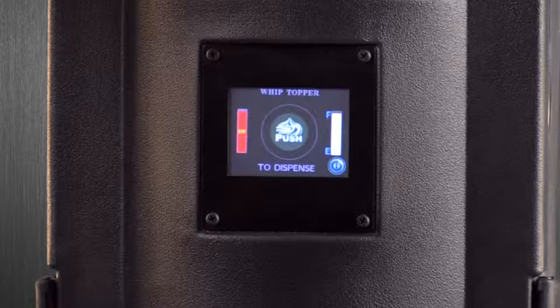Make sure the unit's door sill is properly secured to the door housing as a primary verification. Also, if the unit is showing an excessive temperature reading on the door, for example, plus or minus 200 degrees, it's possible that the temperature probe itself will need to be replaced.